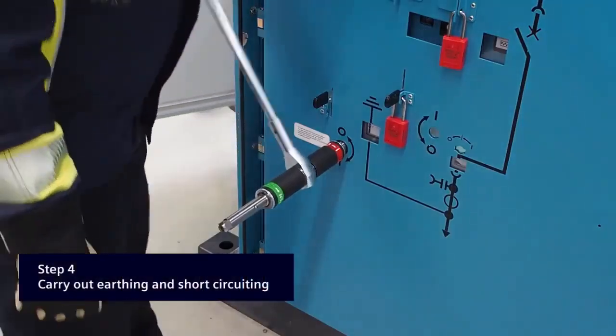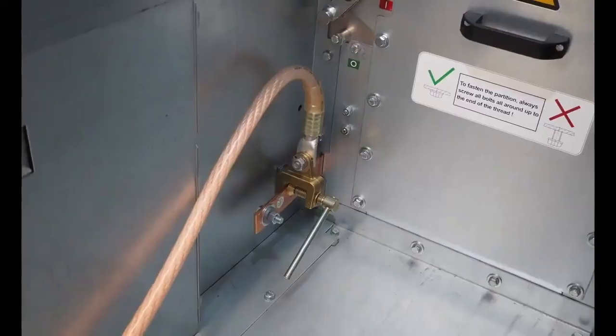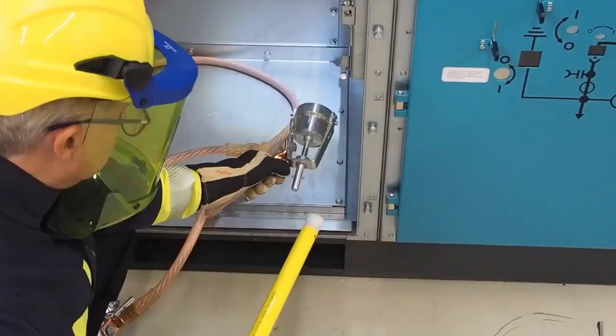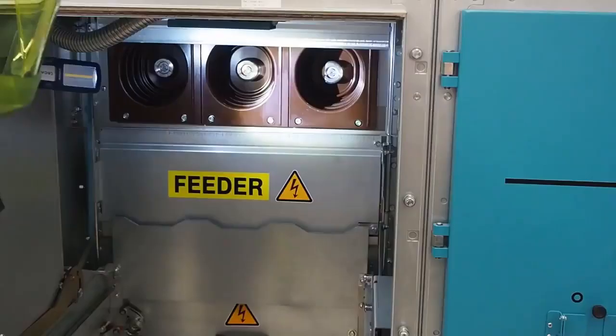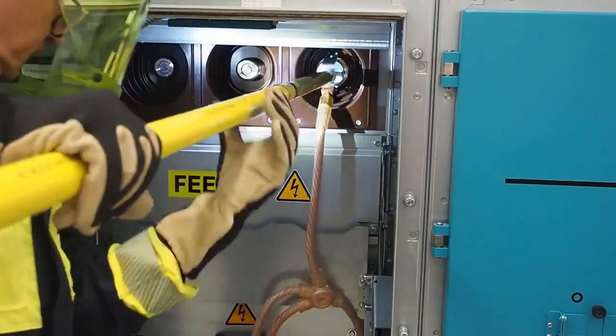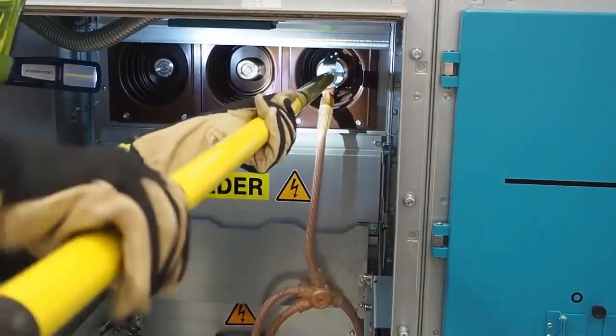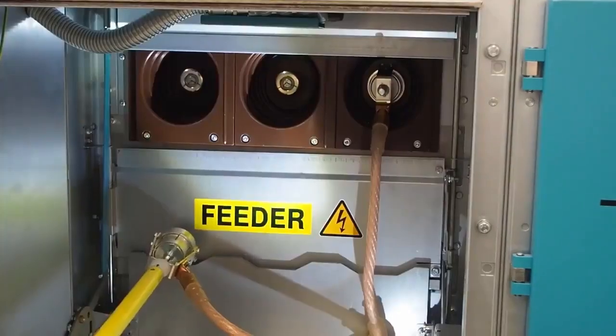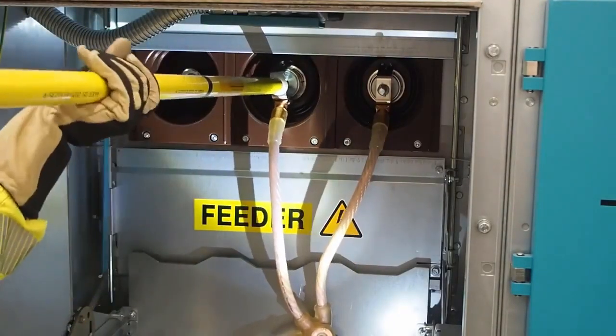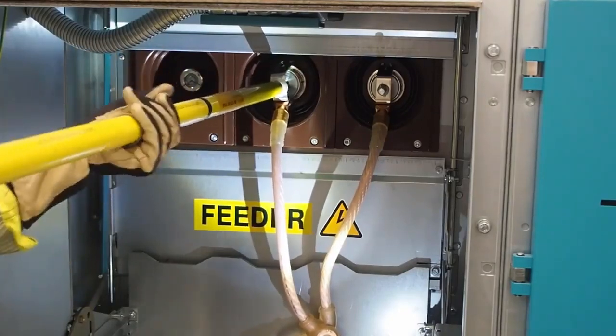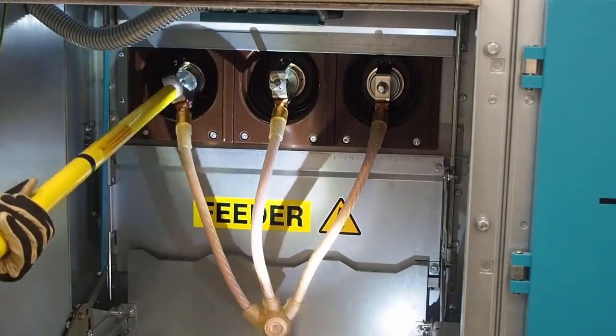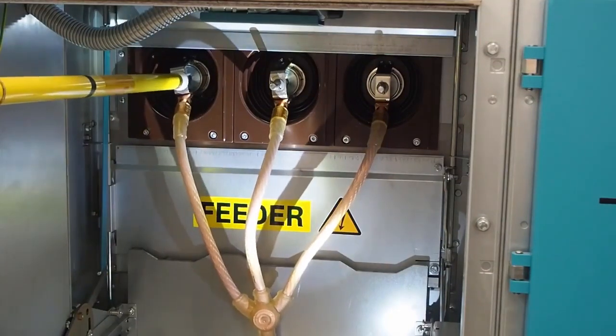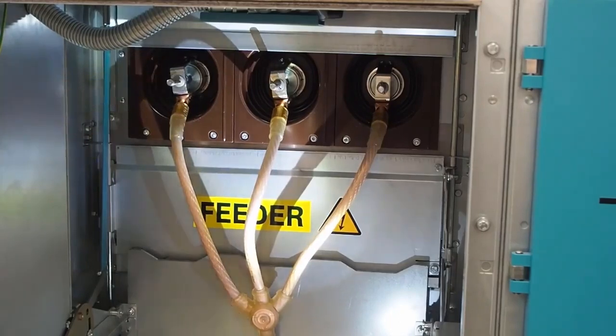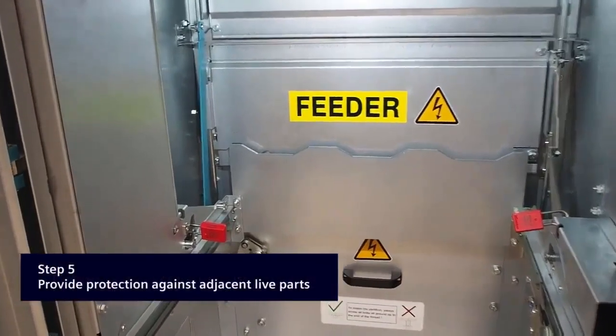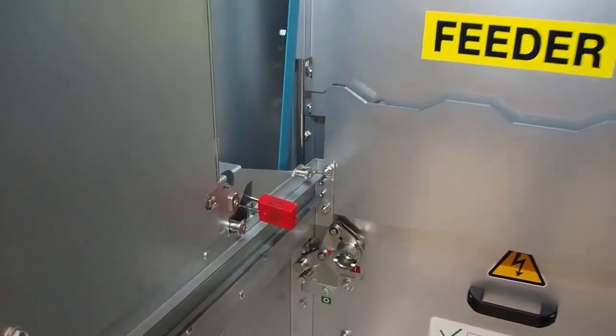The fourth step is to ensure that the busbar and feeder are earthed. You can do this by using the switchgear earthing switch or, if none exists, with a portable earthing kit. The fifth and final safety rule of NXAIR switchgear prevents possible contact with adjacent live parts by locking the respective shutter or by closing all metal covers in the panel.